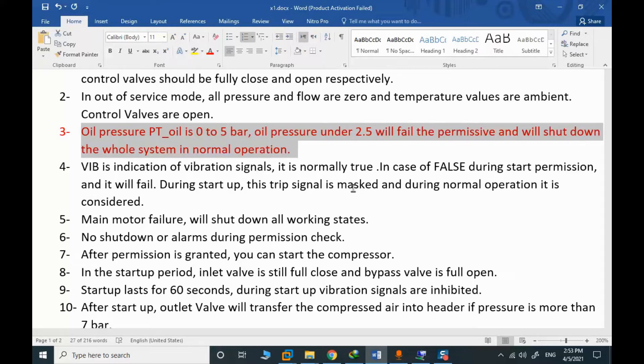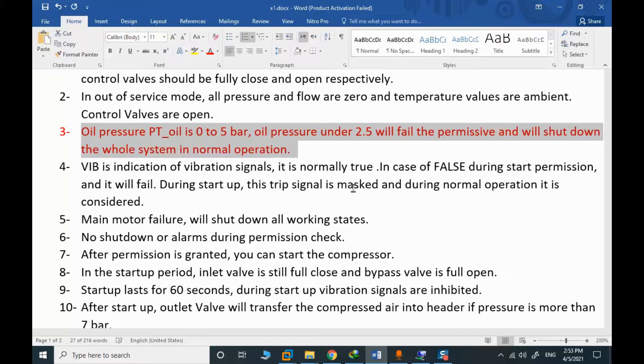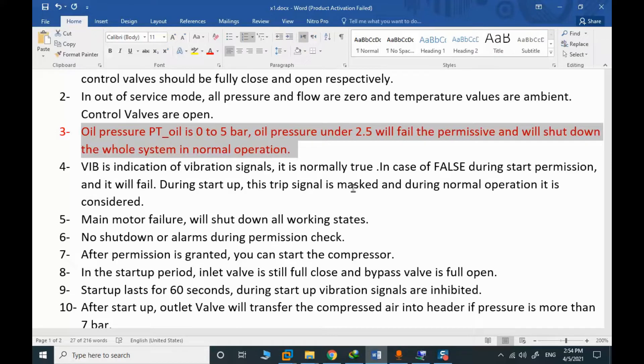Normally there is a trip multiplier. During a startup, the vibrations are a bit high and we will monitor. It's okay for us, for example, to have the vibration level at 80% of trip signal. In some cases, they just ignore the vibration signals during the startup. In this example, we ignore the vibration signal during the startup.